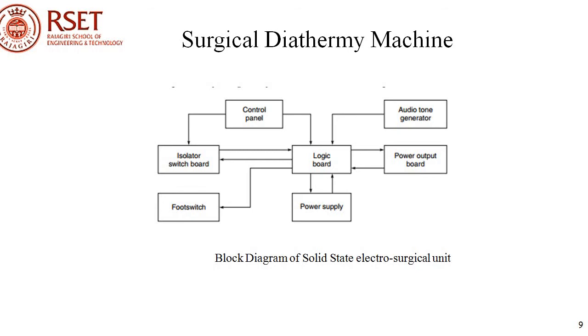Besides these functional circuits, logic circuits are used to receive external control signals and to operate the isolating relays, give visual indications and determine the alarm conditions. A thermostat is sometimes mounted on the power amplifier heatsink. In case of over temperature, it becomes open circuited, signaling an alarm and interrupting the output.